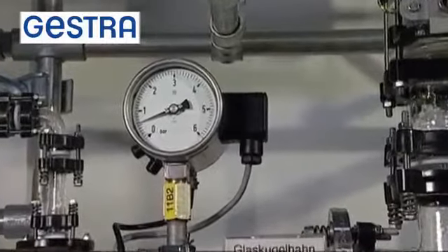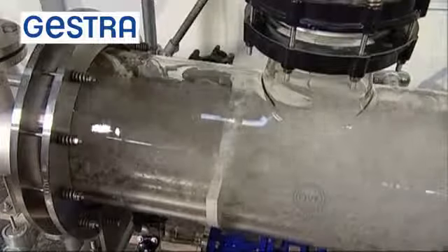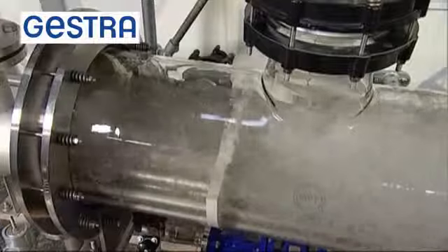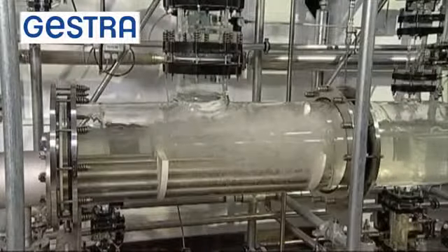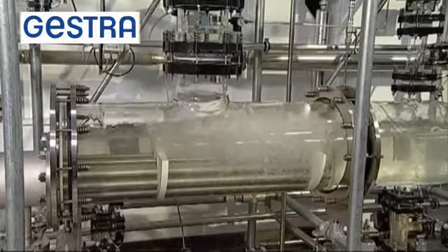To counteract this power dip, the feed water in steam boiler plants is routed through the economizer, where it is preheated through the hot gases of the burner exhaust. More feed water has entered the steam boiler and the filling level has reached 65%. The first droplets shoot up in the steam dome. The steam boiler starts priming.